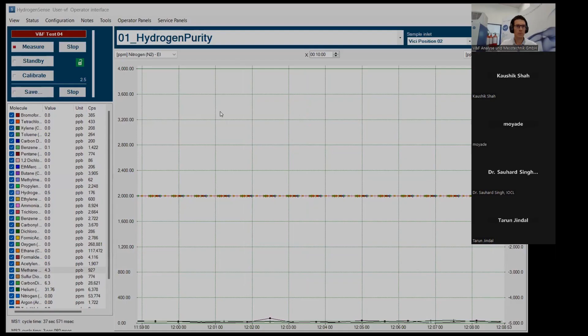If I may, I'll give you a short overview of the software that we are using to control this instrument. So now you should see the main interface of our mass spectrometers. On the surface, it looks quite simple, but loads of things can be set up here. We have different modes of operation: a measure mode, a standby mode, then a calibration mode, which will trigger an automatic calibration. And on the most basic level, we have the possibility to just save data that we want to acquire.